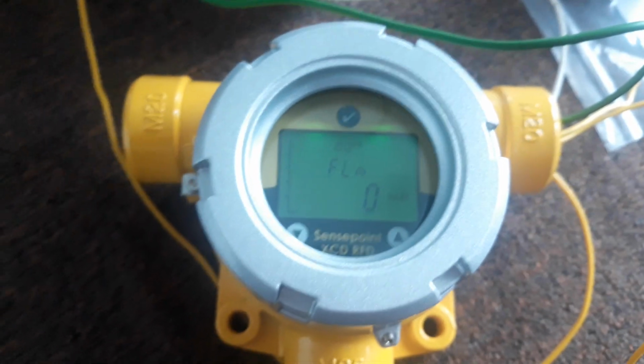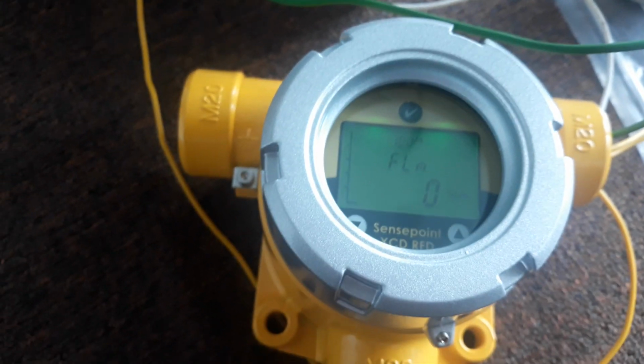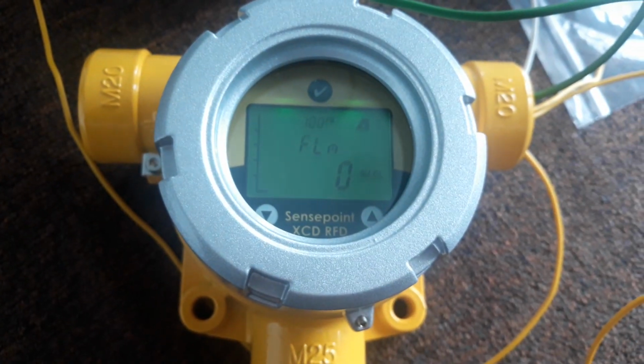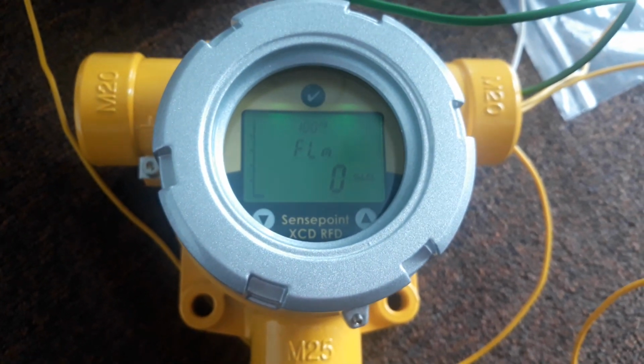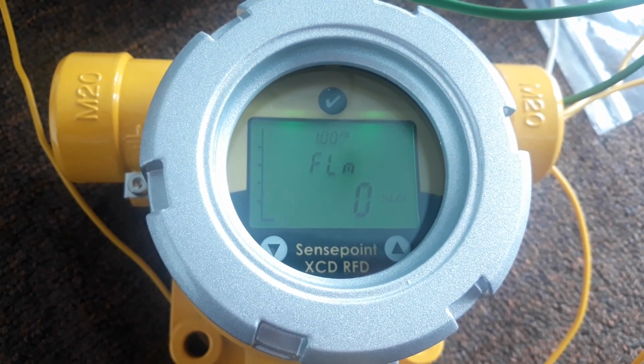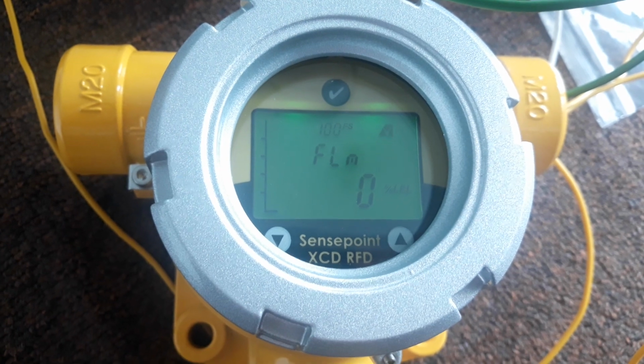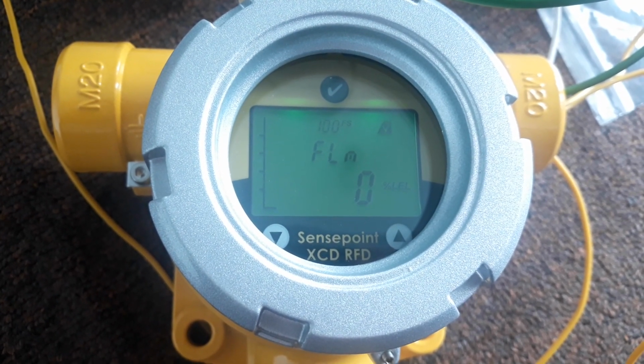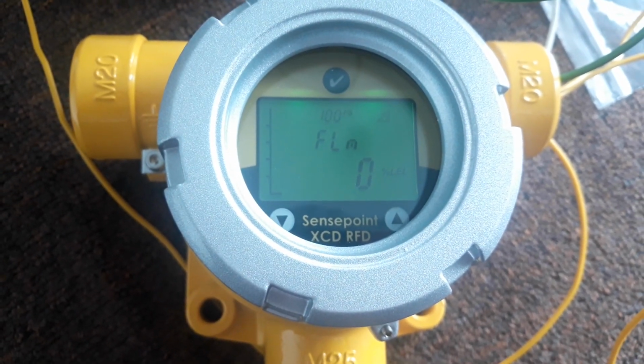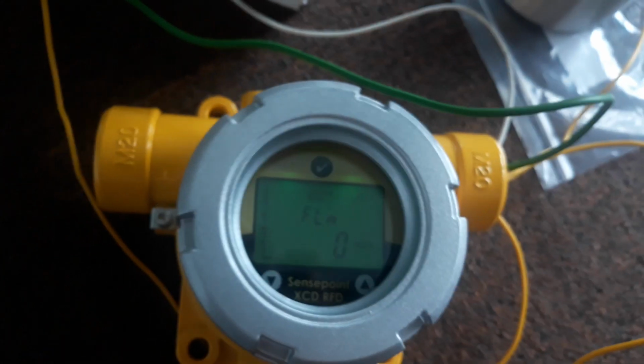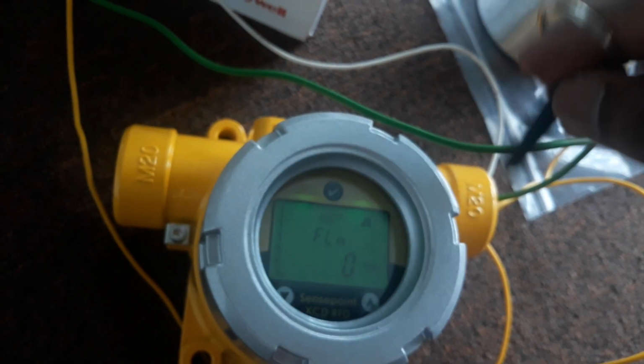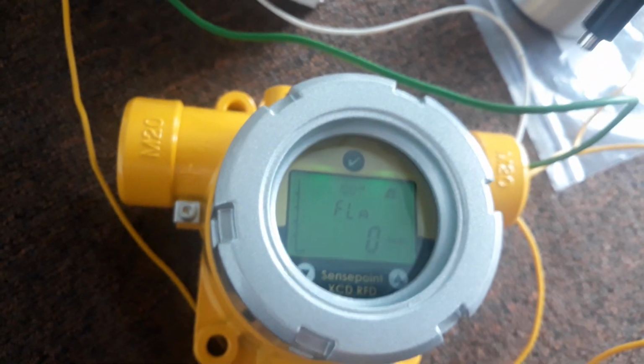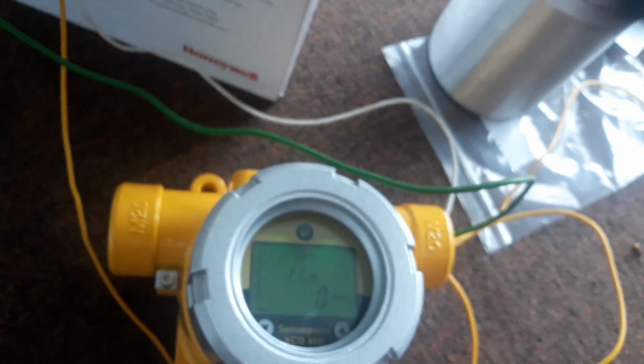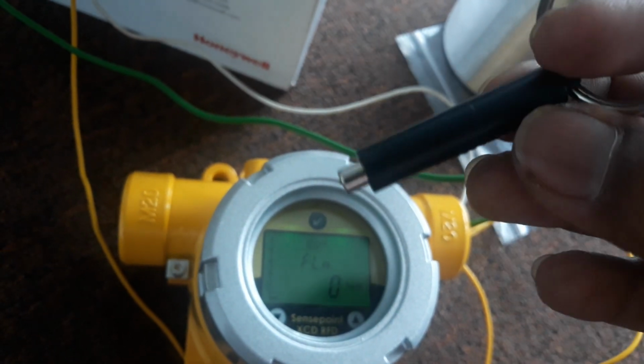Okay, done. If you got a screen like this, the sensor and controller connection is done. So you see something like this. Let's say you got an alarm when you start up, when you warm up. You got the alarm trigger. You must do the air zero first, or zero point calibration. So I want to show you how you can do the calibration and setting alarm. You got the magnet key from Honeywell.